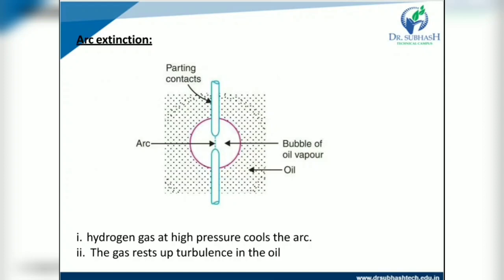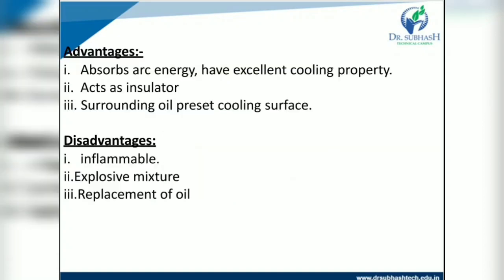After the circuit breaker has interrupted a short circuit current, sometimes the contacts may get burned due to arcing. Also, the dielectric oil gets carbonized in the area of the contact, thereby losing its dielectric strength. This results in the reduced breaking capacity of the breaker. Therefore, the maintenance of the oil circuit breaker is essential for checking and replacement of oil and contacts.